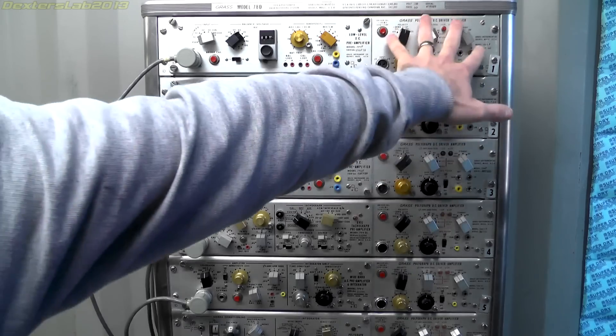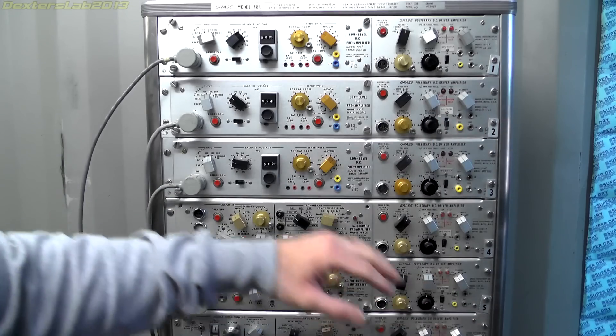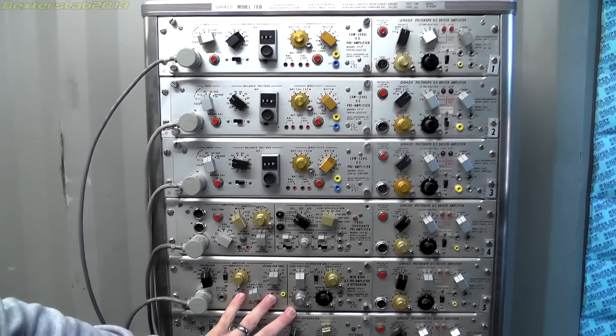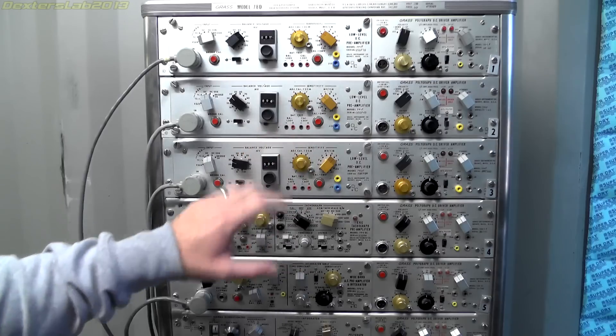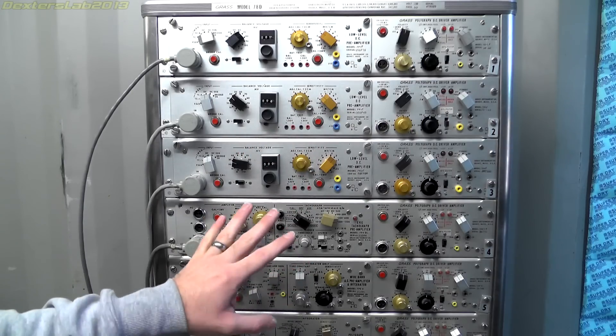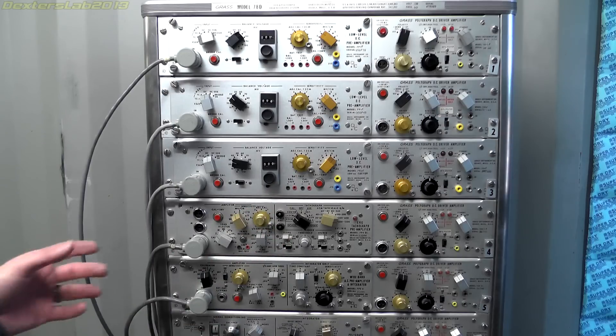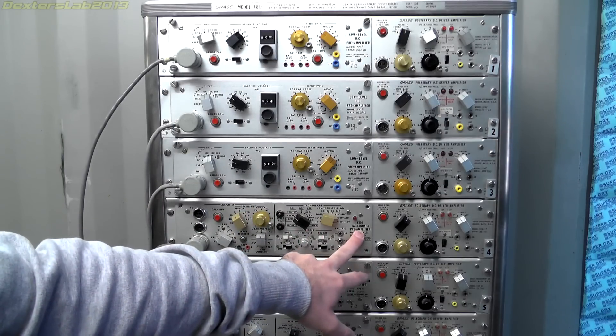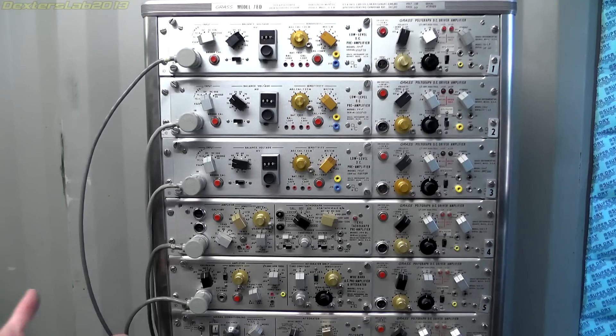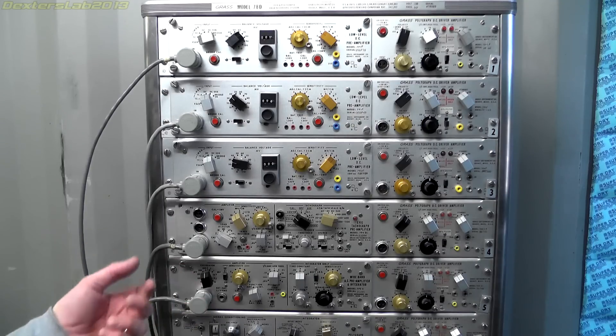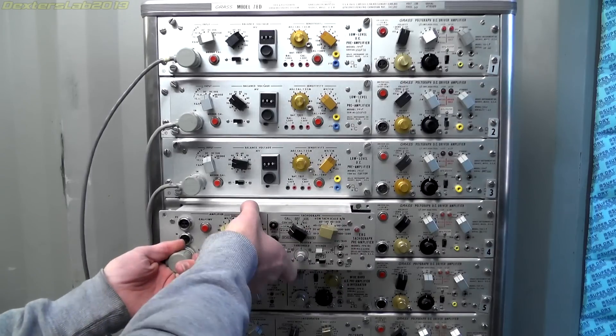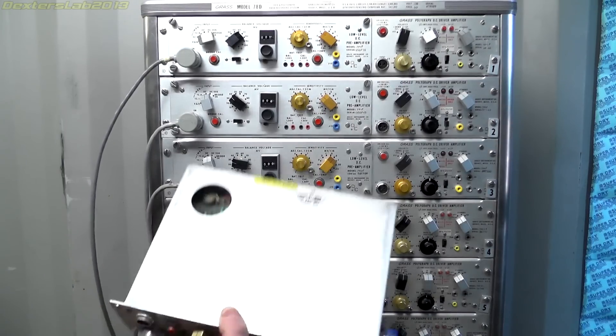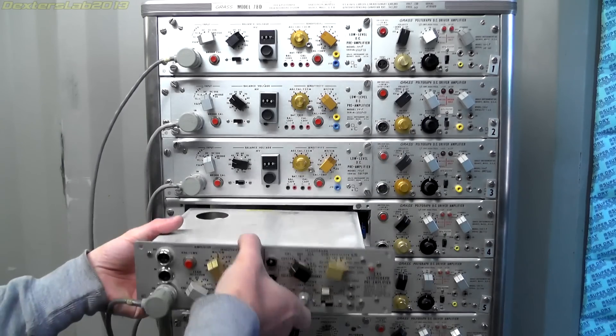This takes the raw signal and is a preamp that's fed into the main DC driver amplifier. It's actually this amplifier here which drives the voice coil in the actual pen. So all these bits here are pretty much fixed but these modules here are interchangeable. And you can actually take them out and swap them with different types of amplifier depending on what you actually want to monitor.